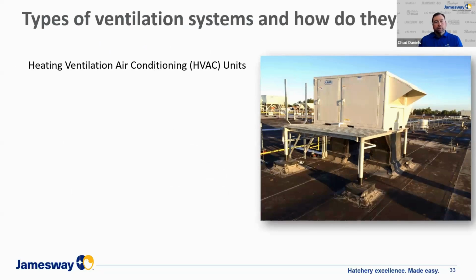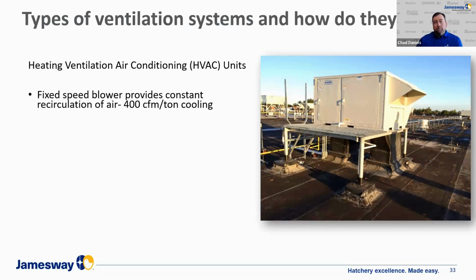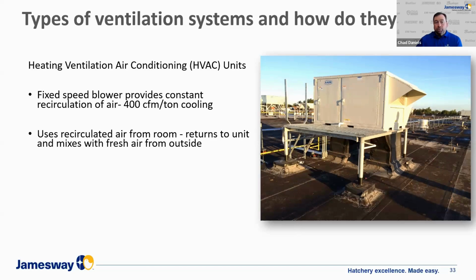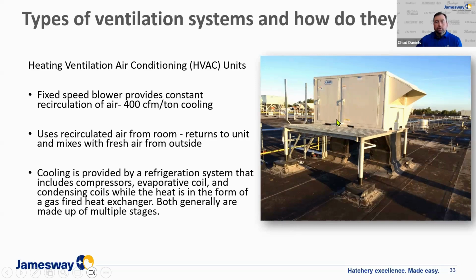So what's probably the most common ventilation system today throughout a lot of the world, especially here in the US market and in Latin America, is rooftop HVAC units. So with these, we know they have a fixed speed blower, provides constant recirculation of air, generally around 400 CFM per ton of cooling. Uses recirculated air from the room, so it returns to the unit and mixes with fresh air from the outside. So you'll see with this unit, there's a duct here that's returning from the room that mixes in the unit with air that comes in through this fresh outside air hood. And that air is mixed and then is first cooled through the unit. And then there's also heating, and then it's provided back into the room.